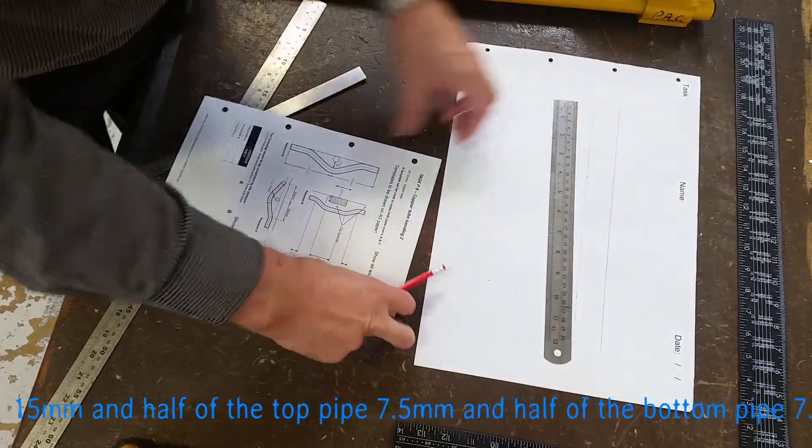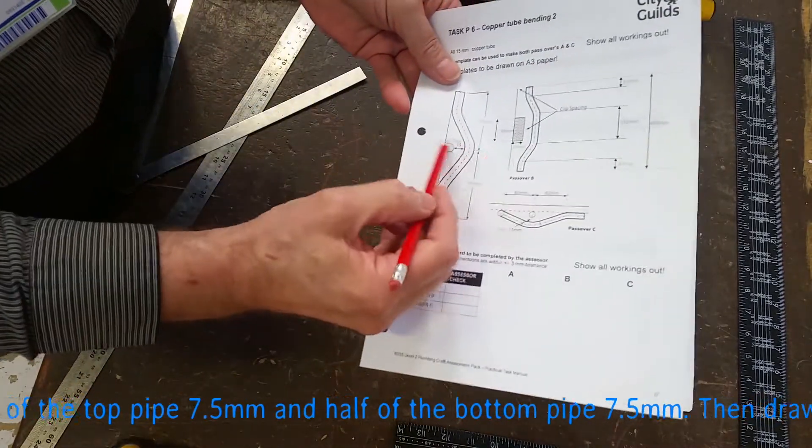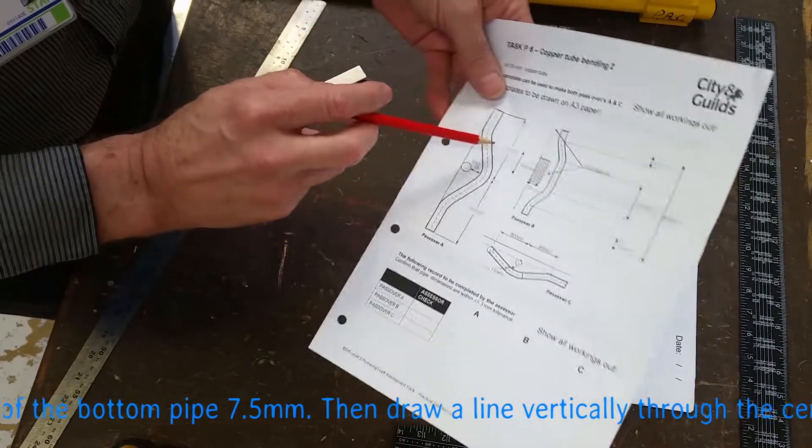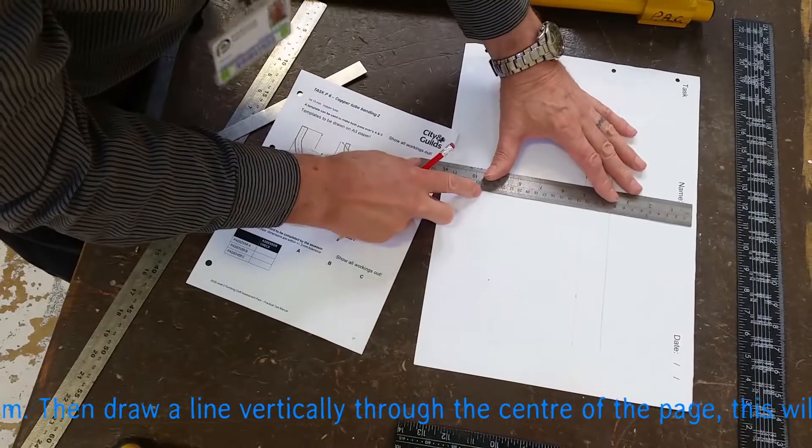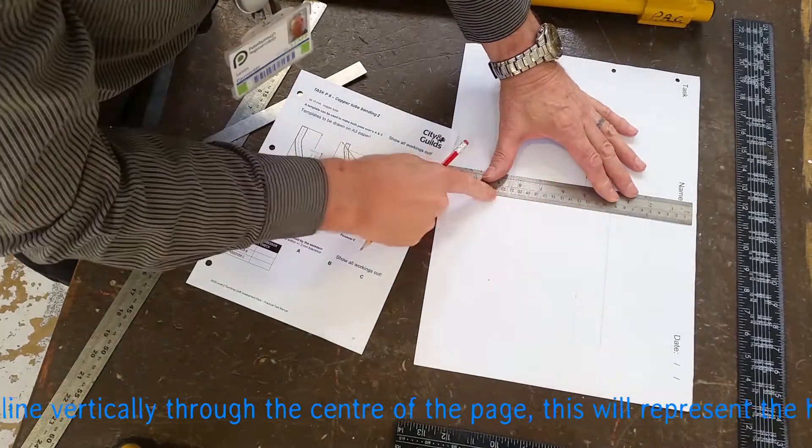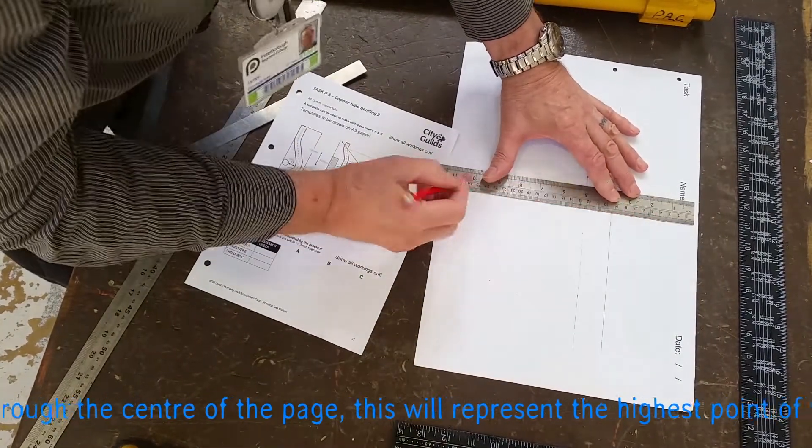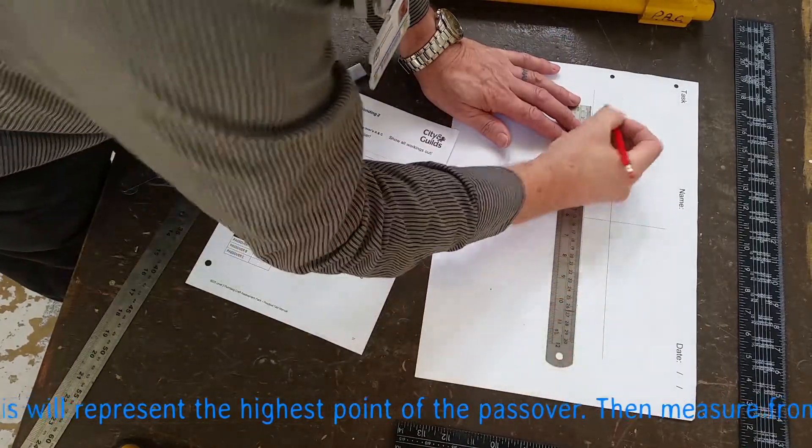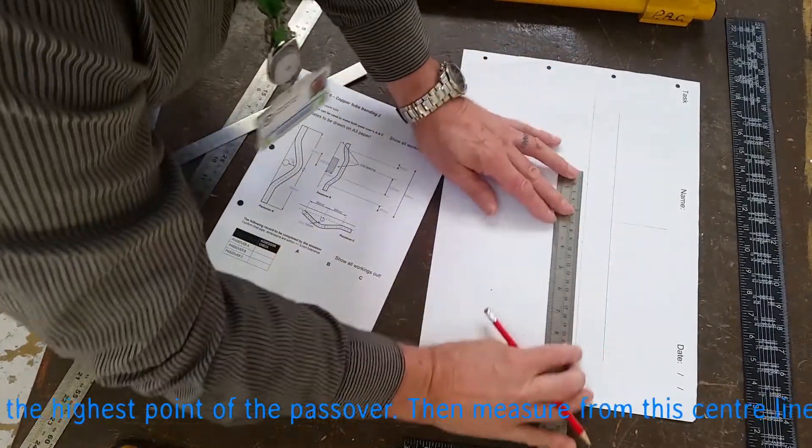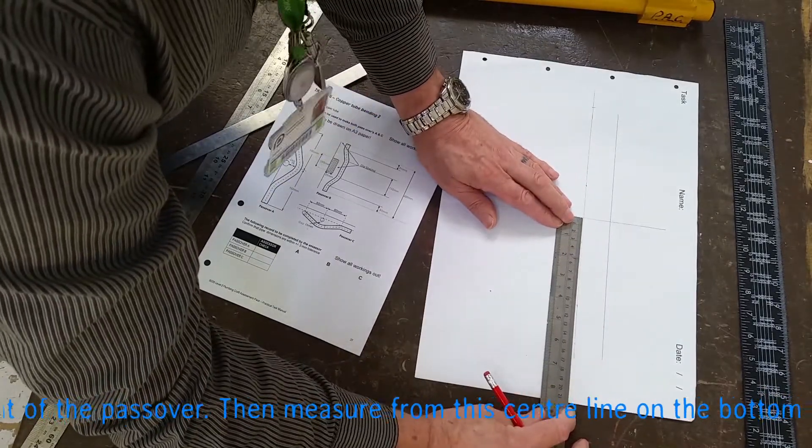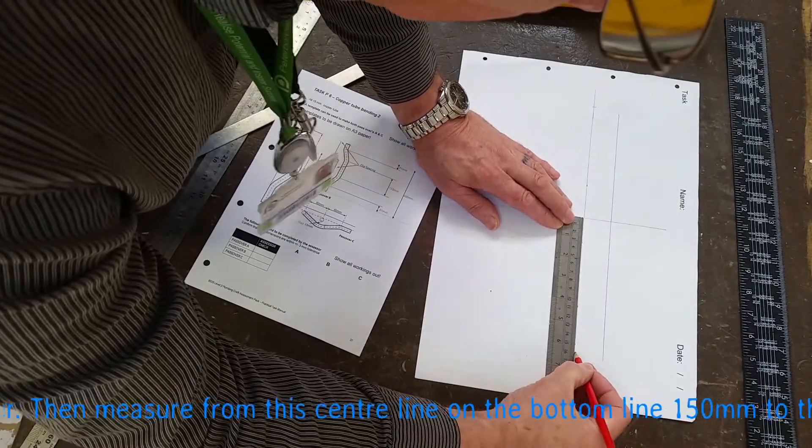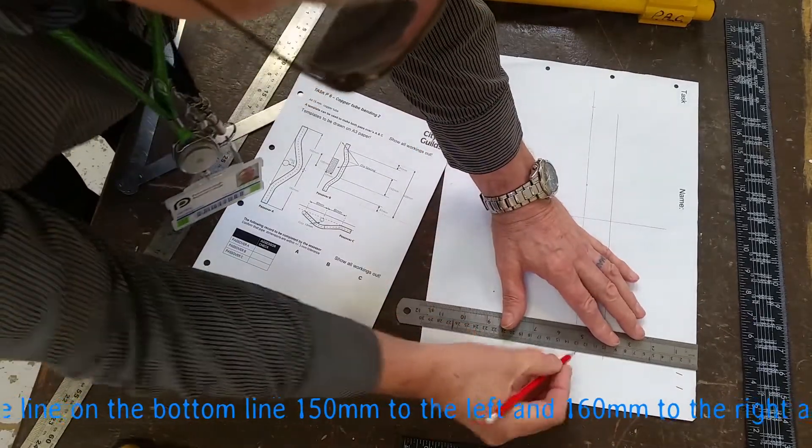The next line we need to draw is the center line, and that would be the highest point of our top bend. So 90 degrees to the lines we've just drawn in the middle of the page, just draw a line all the way through. Then we can measure our end of our pipes, which is on the left 150, on the right 160. Just draw a little line on there so when you lay your pipe on the paper, you can see the line underneath your pipework.